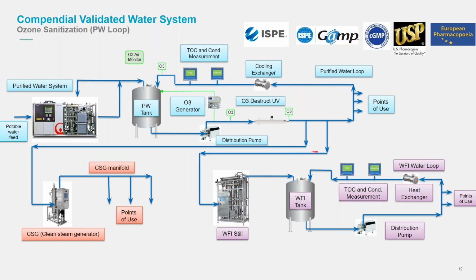And then finally, we come to the WFI system. Here you have a distillation unit, as we talked about before. It heats the water up and changes its phase into steam, and you have to remove any prevailing droplets as they carry the impurities. Then that steam is condensed and feeds into your WFI tank, normally above 80 degrees. In that case, the distribution loop traditionally runs hot, so it'll be running above 80 degrees. And according to the ISPE guidelines, any system that is running continuously above 65 degrees is considered to be self-sanitizing, so you don't need any additional sanitization for this loop. The only thing you have in here is a heat exchanger, which takes care of any temperature losses within the system to keep the system above 80 degrees.